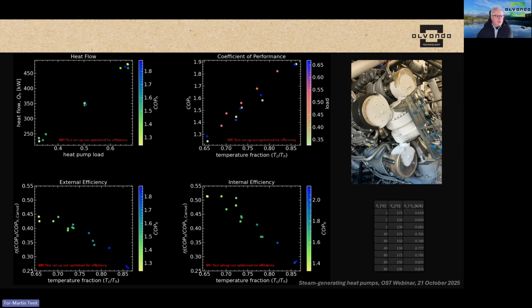You can also see that the off-design behavior of the heat pump is also pretty linear. And if you compare this with the load, shown by the colors, it's also quite linear. So there's not much difference in the COP when it's running on partial loads.